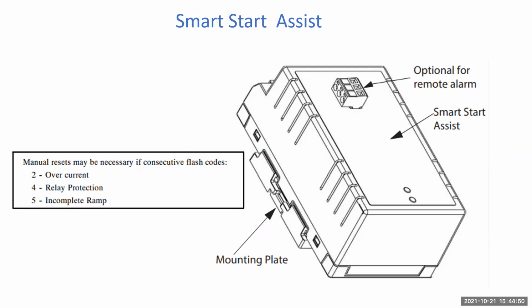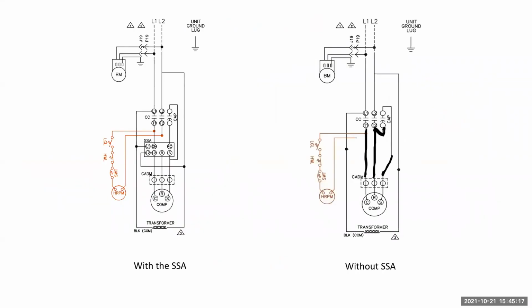De-energizing the SSA is the only way to really override its built-in time delay. The SSA can be removed from the system, and you will have to rewire the compressor and the capacitor. Also, the SSAs are no longer available. So once you remove one and you're still having issues, you can put in a hard start kit.